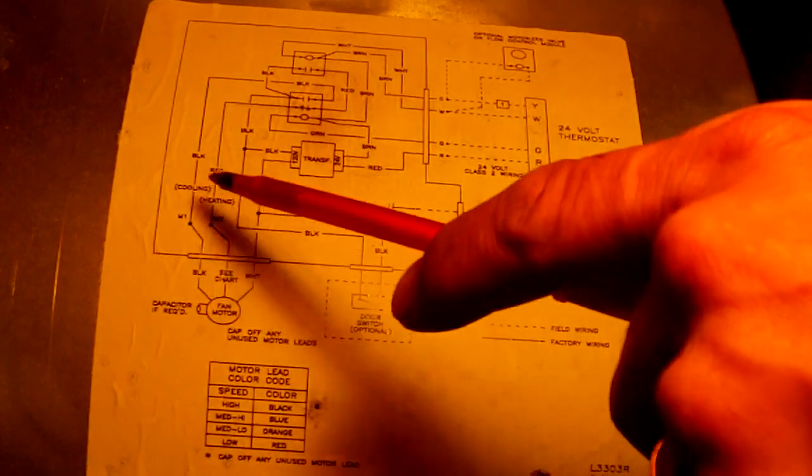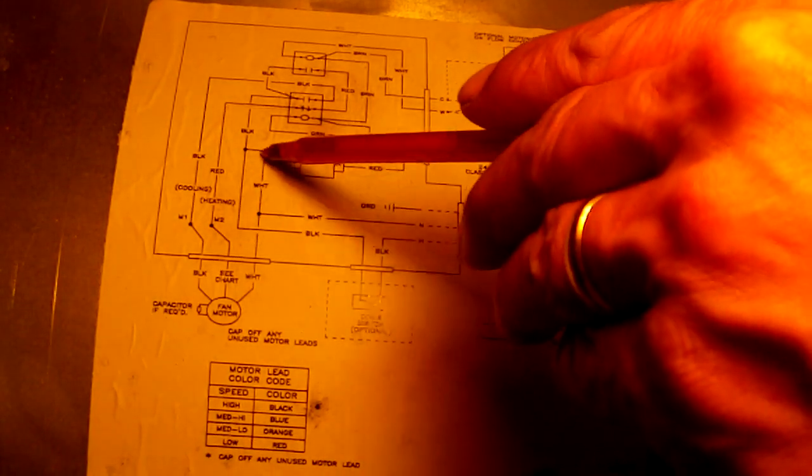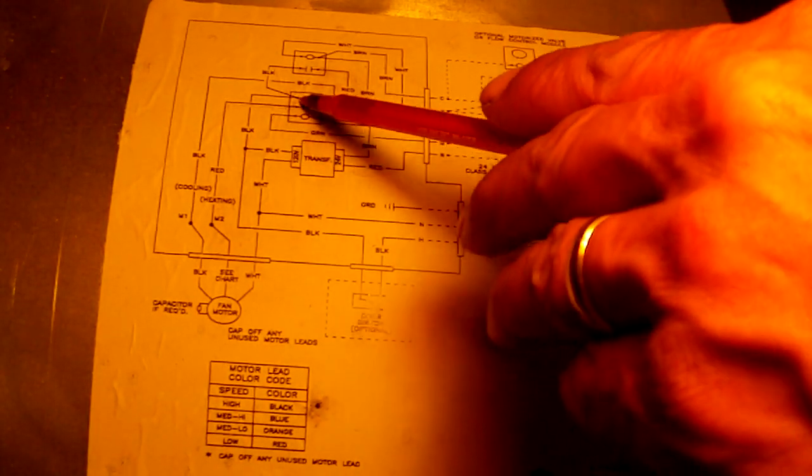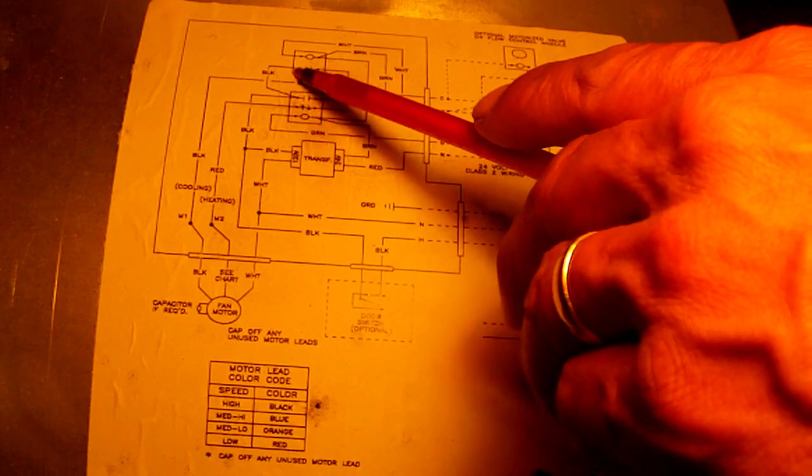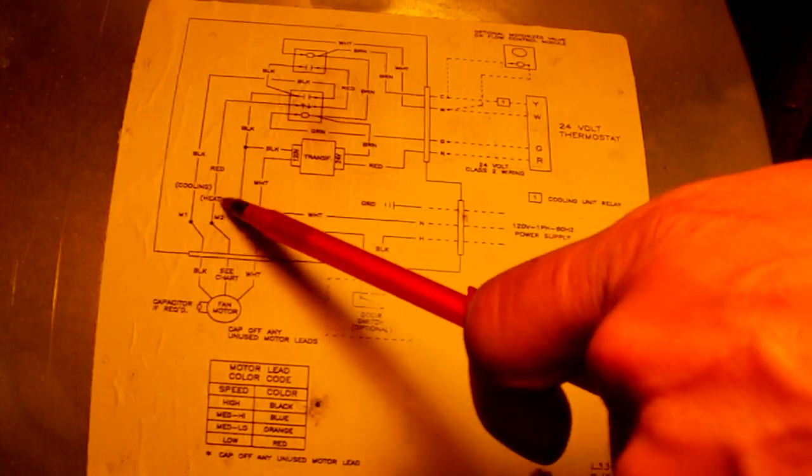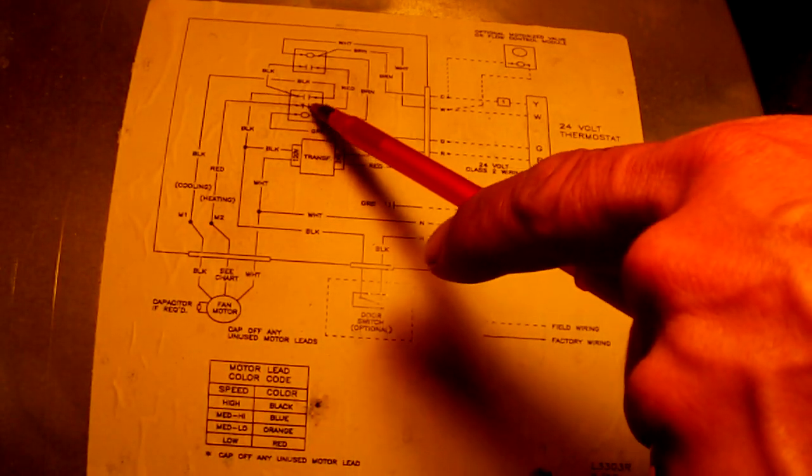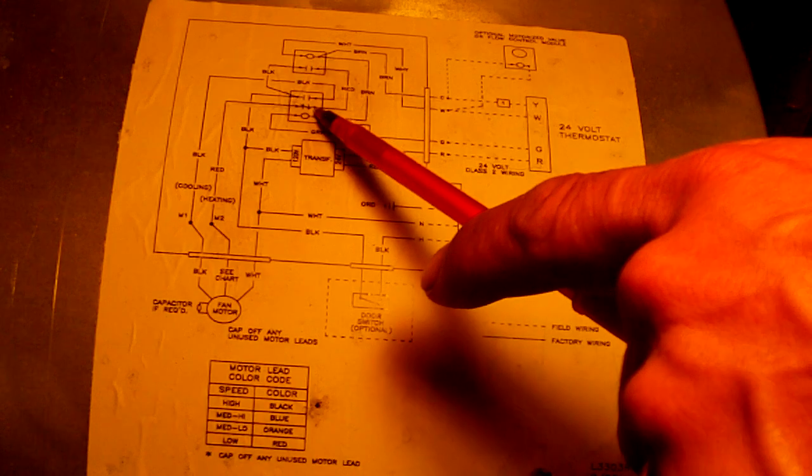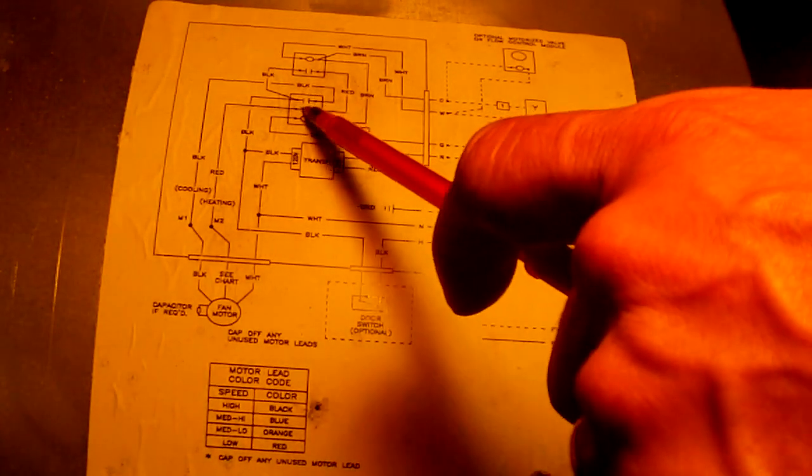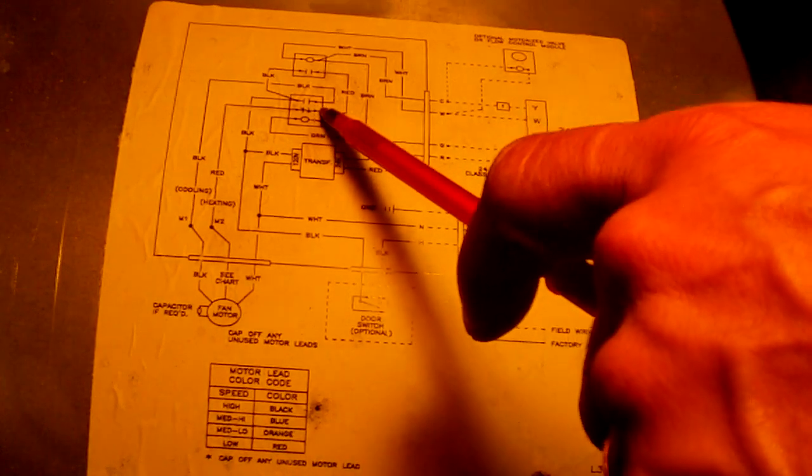That's the circuit right there. L1 goes around, powers the transformer, powers the relay, powers the heat sequencer, goes around through here. This is a relay with normally open and normally closed contacts. It's like a two-speed - they use this type for two-speed.